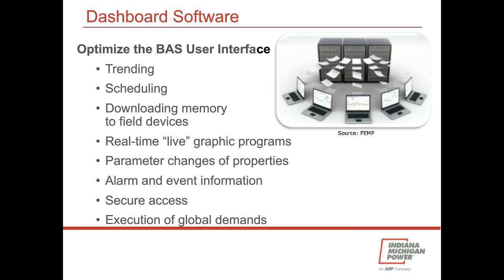We need to interact with all of this hardware, and we do that through a building automation system user interface. What's involved with that? You're looking at trending data, doing some scheduling, looking at real-time live graphic programs that do a really good job of mocking up the actual air handler, fan, or cooling tower, giving you flows and temperatures in real time. There's also alarm and event information you'll be seeing.